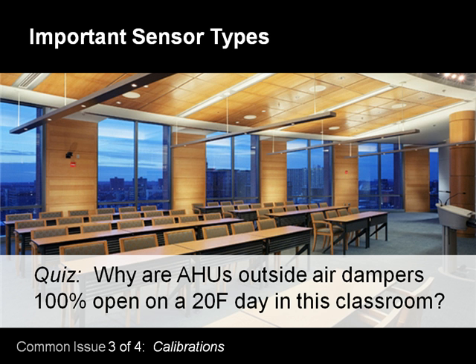I come to find out that they have CO2 sensors in these rooms, and they have a demand control ventilation system that opens up more outside air to try to get the CO2 levels down. These sensors are off by 100 parts per million, so they are far out of calibration. They think it's 2,500 parts per million in this auditorium. It was actually a teaching classroom. And that was pushing the demand ventilation control open. All the dampers were wide open, 20 degrees outside, and the steam heat is blasting away trying to heat the air back up, and then it was overheating, and the cooling coil was running to cool it back down to 55 degrees. It was like, this is unbelievable. You would think, how can this be? But that's the God's honest truth of what you run into out there. Every job I go on, I'm seeing it.